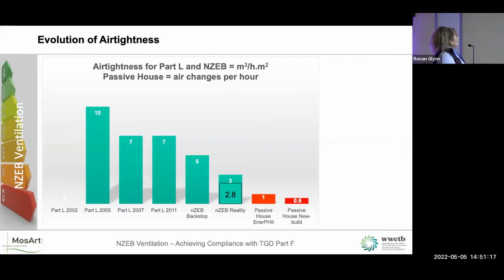So where has air tightness been going? I suppose the regs Part L 2002, there was no mention of air tightness. Then 2005, 10 was acceptable. 2007 and 2011, we were down to 7 meter cubed per hour per meter square. So that all changed in 2019 with the backstop going down to 5 meters cubed per hour per meter square. And as Emmanuel pointed out, 2.8 is the NZEB reality at the moment. Again, we know that between 3 and 5, we're allowed to have natural ventilation, but there have been houses that have slipped under the radar and they've been naturally ventilated and they're actually too airtight for it.